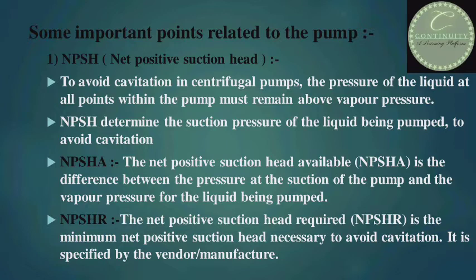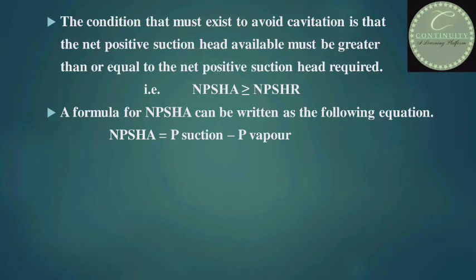NPSHA is the net positive suction head available, defined as the difference between the pressure at the suction of the pump and the vapor pressure of the liquid being pumped. NPSHR is the net positive suction head required — the minimum NPSH necessary to avoid cavitation, specified by the vendor or manufacturer. The condition to avoid cavitation is that NPSHA must be greater than or equal to NPSHR.